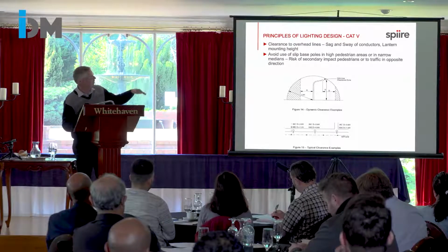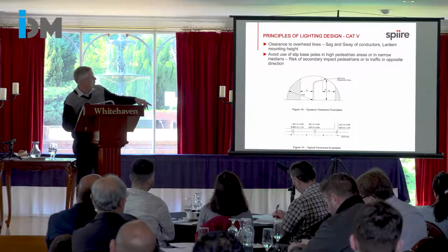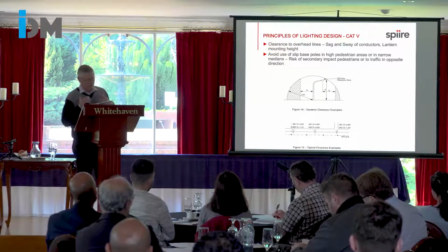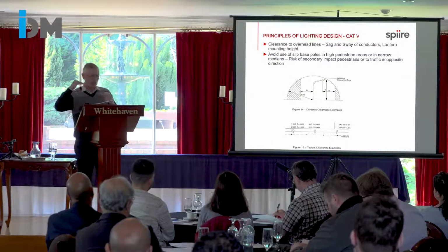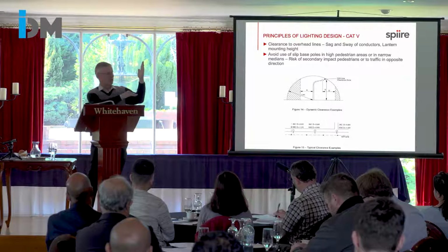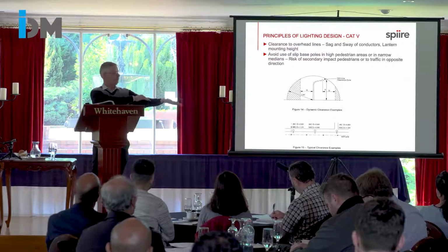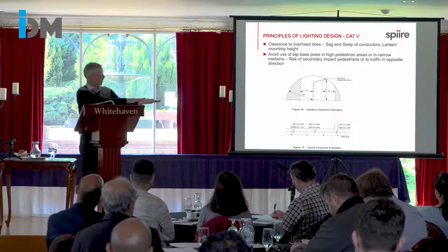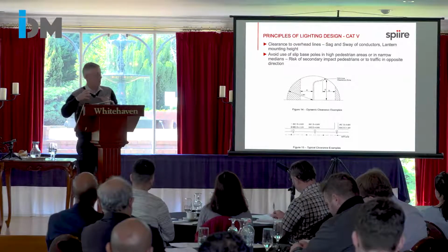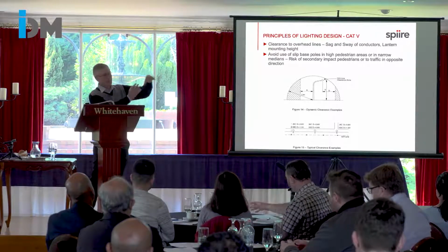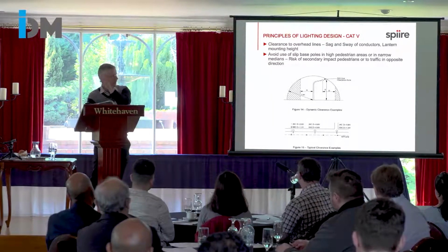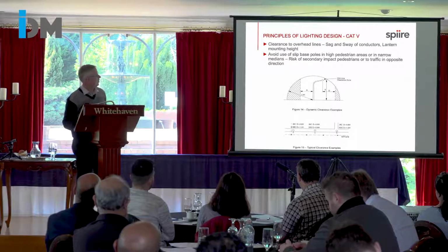Check, because that's clearance below the power line as well as to the side of the power line, because the impact absorbent poles are designed to basically fold as the car runs over it, but then they'll whip sideways or whip forward as the car or truck runs further over it. Slip base poles, on the other hand, are designed to just fly off at the base, and then they'll potentially, depending on how hard hit, career horizontally across the ground and then lay flat on the ground. And you just don't know whether or not that's going to move horizontally, depending on how high the vehicle is that hits it. That's an important design aspect.